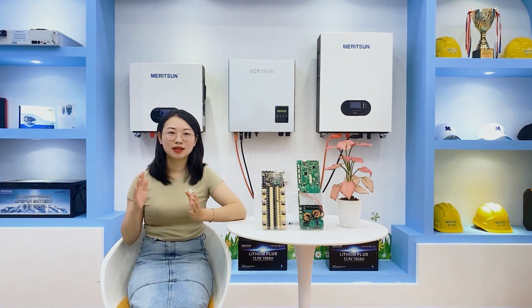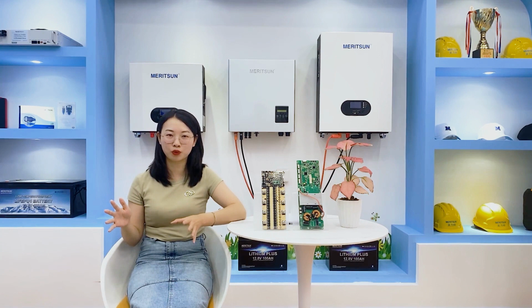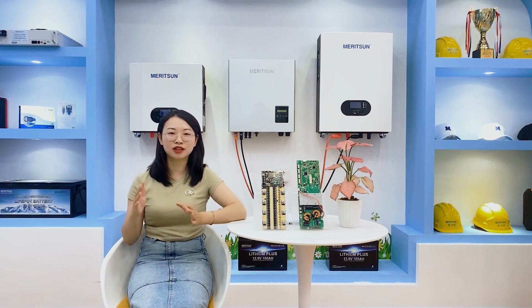With large batteries which have low source resistance and powerful loads which have large capacitors across the input, the inrush current can easily peak at 1000 amp. Such a large inrush current is much greater than the current during stable operation and the current that the inverter can withstand, which will cause the inverter to be damaged by the battery. The pre-charge circuit can supply power to the inverter with a small current when the battery and inverter are connected together, until the battery supplies the inverter with a relatively stable and low current.